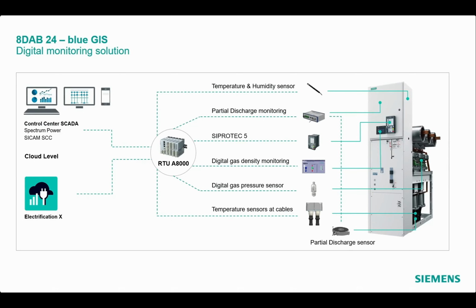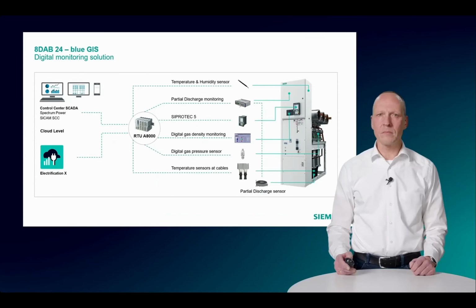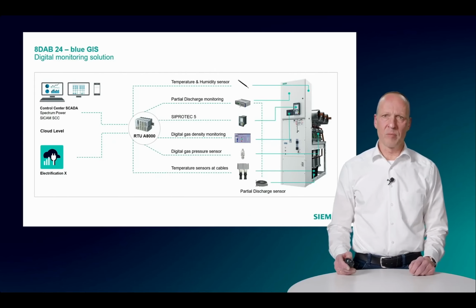Temperature and humidity monitoring with PT1000 temperature sensors installed around the cable connectors and humidity sensors which can be installed within the switchgear and inside the switchgear room. Circuit breaker can be monitored with the I2T method with the help of the SIPROTEC 5 protection device.